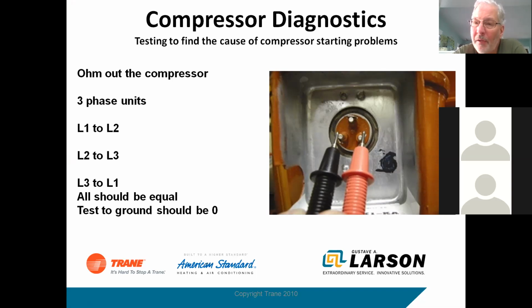If you get into inverter drive equipment, and I didn't put anything on inverter driven equipment in here, and that includes the Mitsubishi, the variable speed condensing units, heat pumps, those typically are a little lower. They're like 0.7, 0.8, sometimes 1. Some of those are down to 0.2 for ohm value on inverter driven equipment. But that is basically a three-phase compressor also. So you ohm them out the same way.